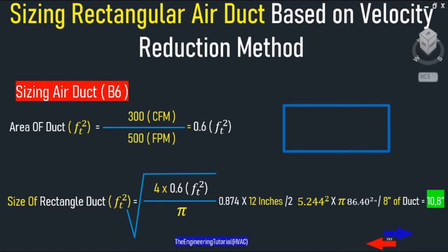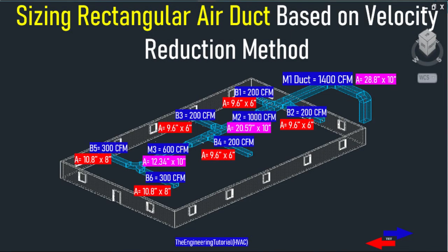Next, 300 CFM divided by a design velocity of 500 FPM, square root of 4 times 0.6 divided by pi, times 12 inches divided by 2, squared, times pi. That gives us 86.40 square inches. Dividing 86.40 square inches by 8 inches height gives 10.8 inches by 8 inches.